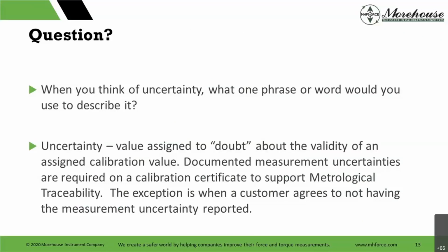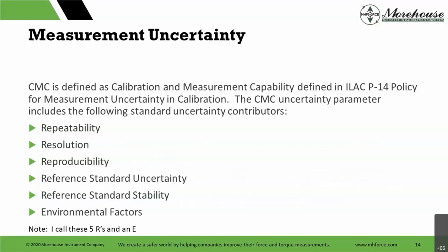Okay, so when you think of uncertainty, one phrase that you would use to describe it: uncertainty, value assigned to doubt about the validity of an assigned calibration value. Documented measurement uncertainties are required on calibration certificates to support metrological traceability. For those that know, NIST has performed some very good classes on uncertainty, and one of those polling questions was, what word do you most associate with uncertainty? Like 90-some percent of that population, it was 100-some people, said doubt about the validity. So that's why this slide is here, to further help explain that. But then we look at what really is uncertainty. CMC, a lot of people shorten this, right?